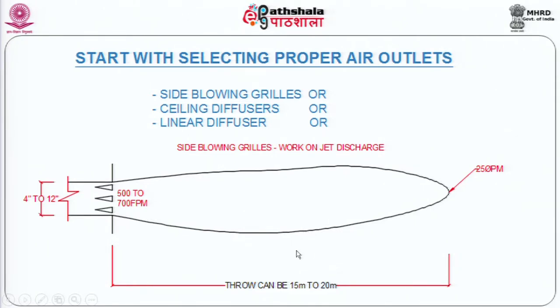This is best done by keeping the jet grills higher than the occupied area. In other words, air conditioned air is dissipated into the unoccupied zone. Now, this might look like a contradiction, but it is an essential requirement. Good supply air design calls for air to be discharged in the unoccupied zone, and the high air movement caused by it will give you induction in the occupied zone.